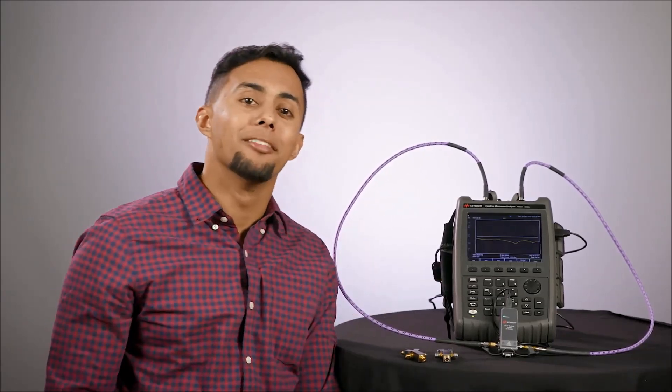Today there's an awesome alternative to traditional mechanical CAL. It's called electronic calibration, or e-CAL. An e-CAL module is a solid state calibration module, which makes two port calibration fast, easy, and less prone to operator errors. It has a simple setup and you get excellent accuracy without spending a bunch of time to calibrate.